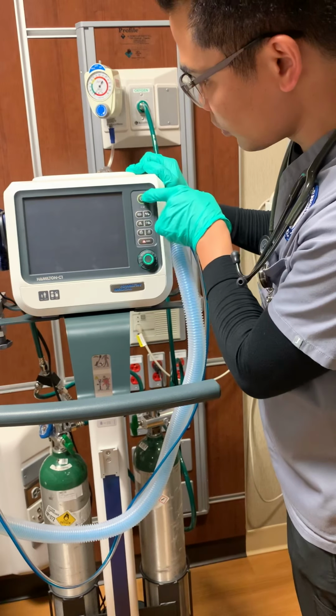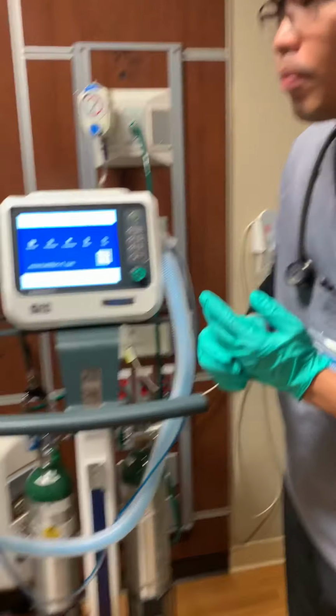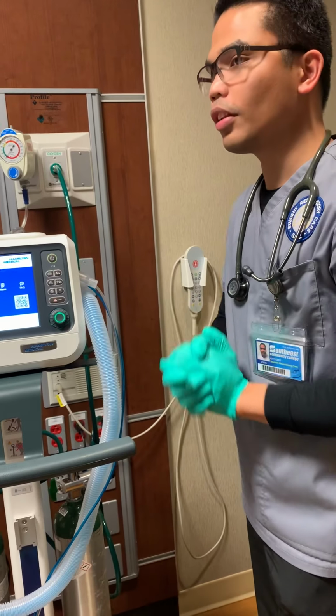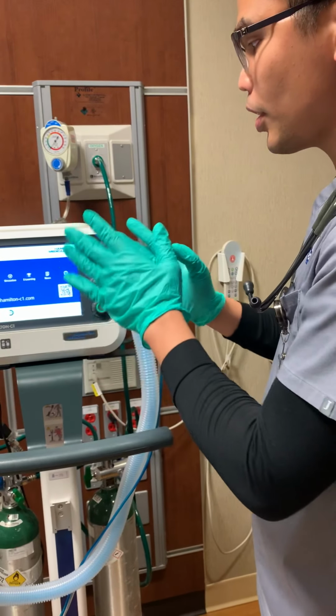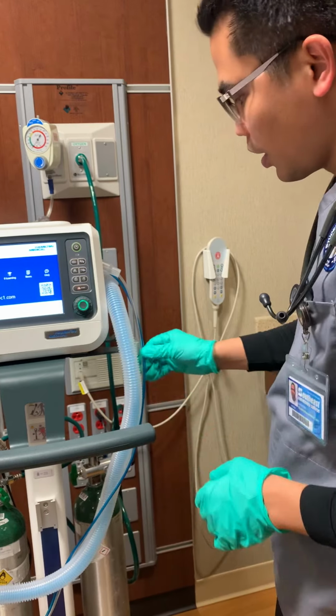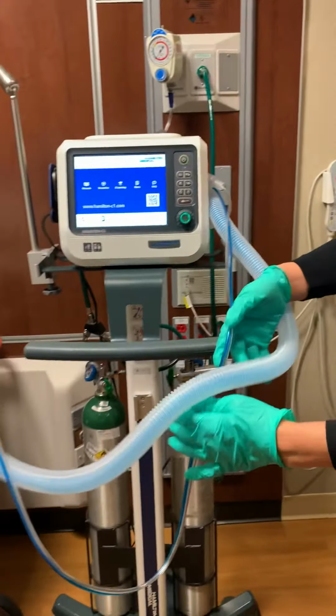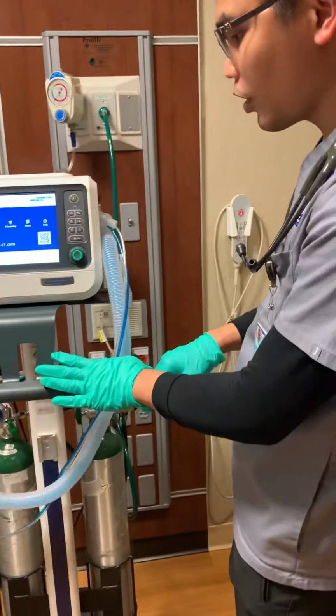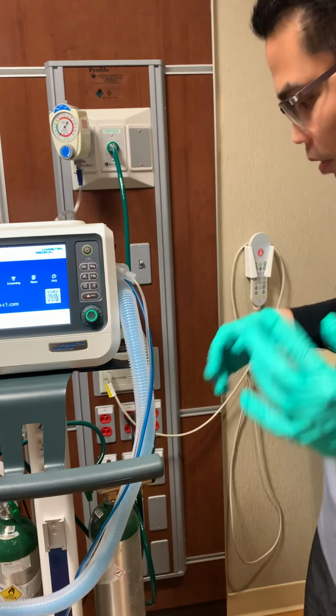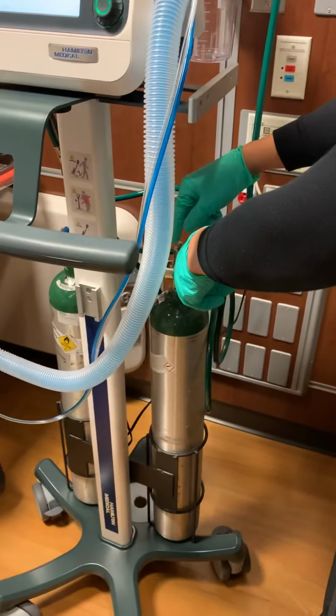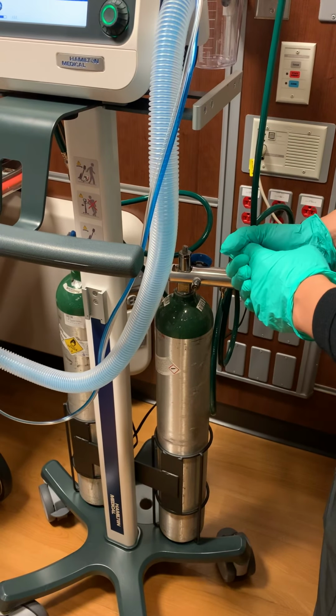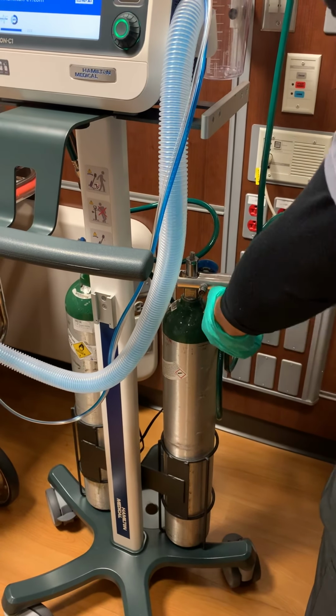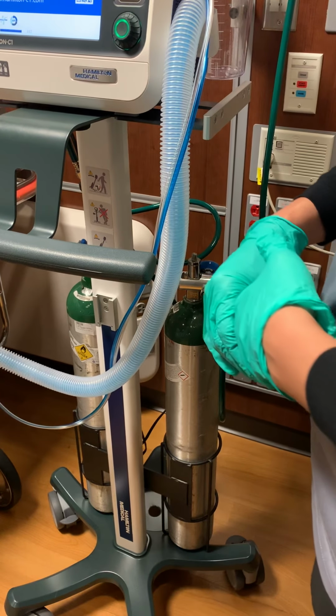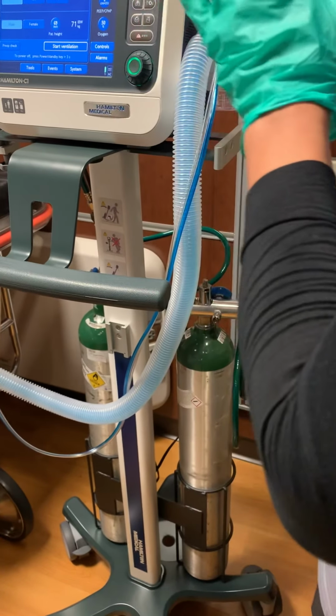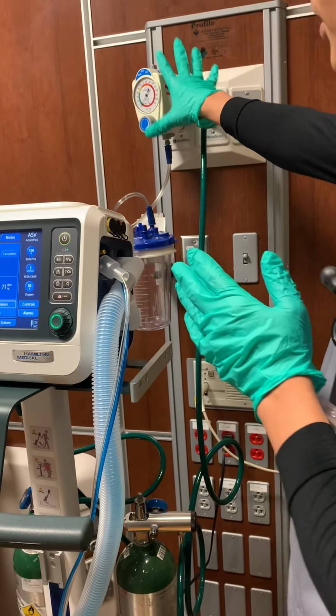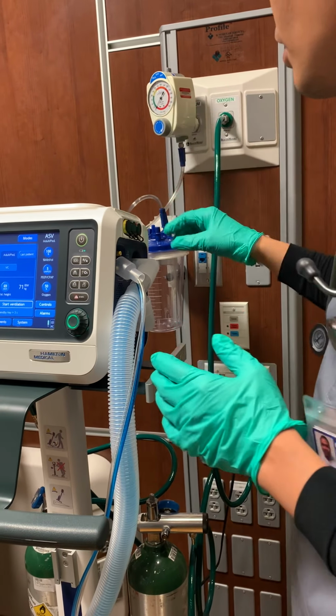So this will take a couple of seconds, about up to a minute. So while we assemble, make sure we inspect also everything, such as if there are any kinks on this flow sensor. And then with this ventilator, because this is a transport ventilator, make sure we inspect the O2 tanks, both of them, if it is complete or if it's full. So that way we don't have to keep on grabbing a different O2 tank.